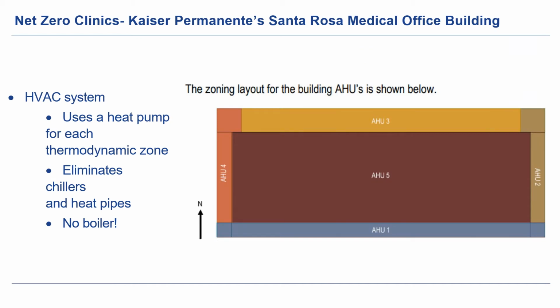In fact, the primary HVAC design strategy was an all-electric system—a series of heat pumps, no chillers, and most importantly no boilers, no gas line. On this site, eliminating the natural gas line and the piped heating distribution saved the project $1 million.